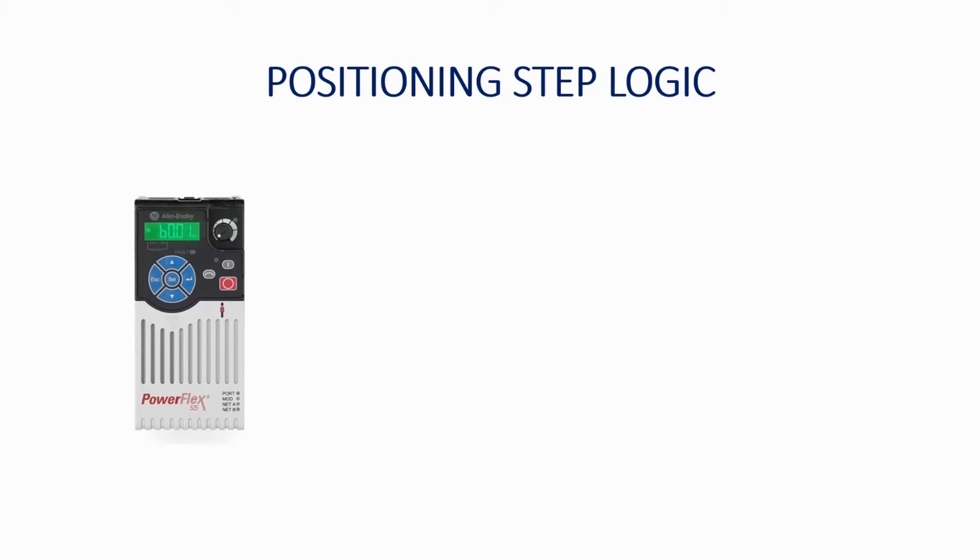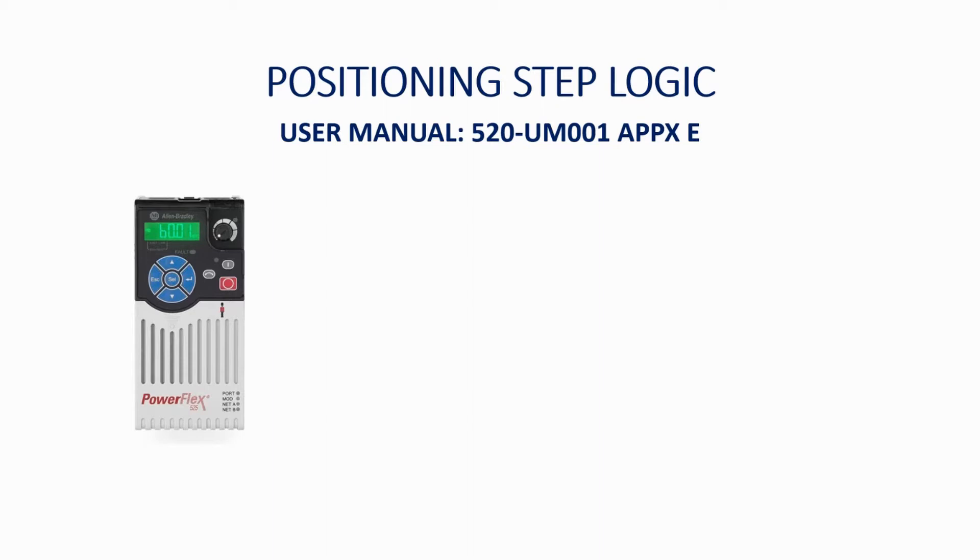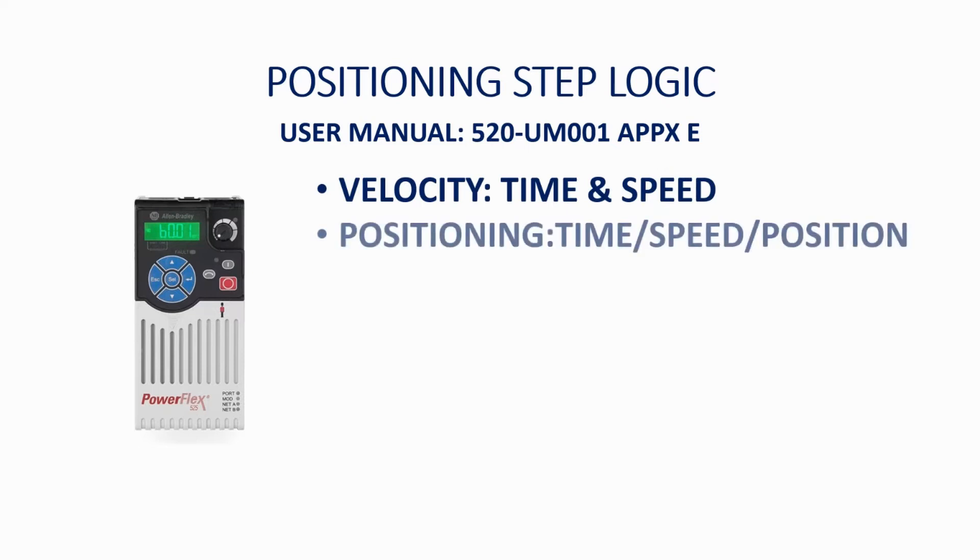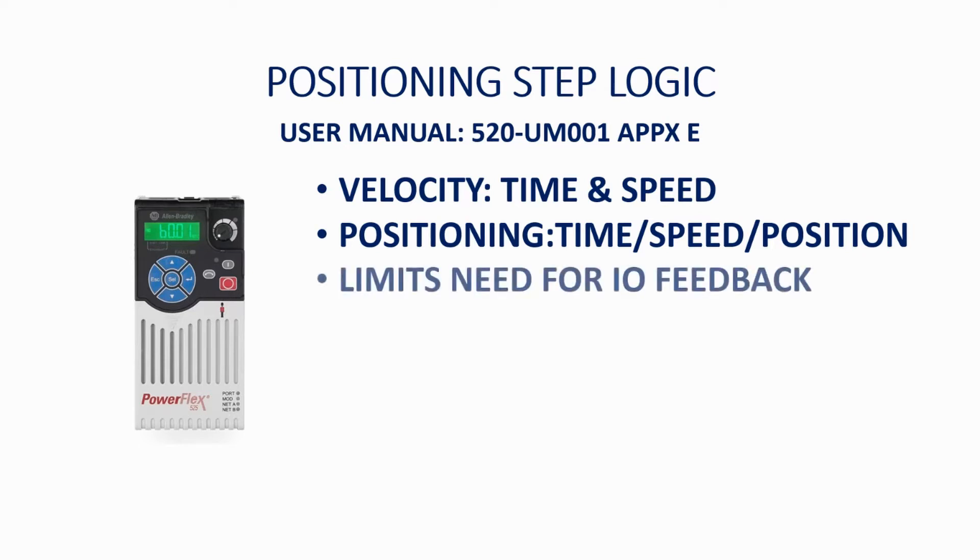Positioning step logic with the PowerFlex 525 is described in Appendix E of the user manual. Positioning step logic differs from velocity step logic in that velocity logic accounts only for time and speed, whereas positioning logic accounts for time, speed, and position. This limits the need for feedback and I.O. into the system in order to control motion.